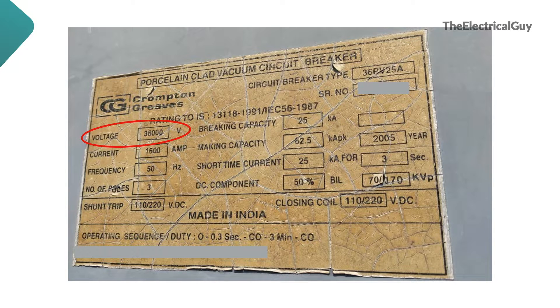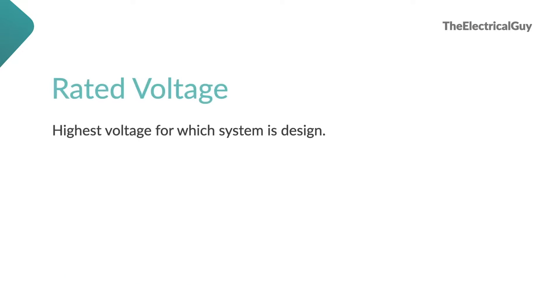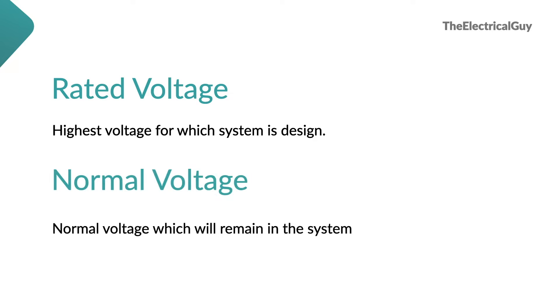Rated voltage is the highest system voltage for which the breaker is designed. This voltage is mentioned in kV-RMS or Volt-RMS and it refers to the phase-to-phase voltage of a three-phase system. People often get confused between rated voltage and normal voltage. Rated voltage is the highest voltage of the system for which the system is designed, whereas normal voltage is the voltage which remains in the system normally. So in this case, 36 kV is the rated voltage and 33 kV is its normal voltage.